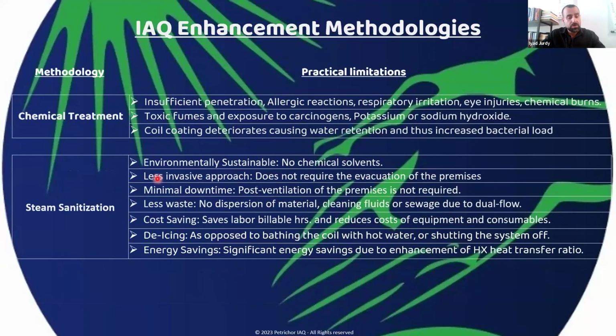The two most common procedures you'll find out there are chemical treatment and steam sanitization. Chemical treatment is the conventional way, the only way before we started using steam, which gives better results. With chemical treatment, we use a small hand pump and literally spray chemicals, acid, on the front of the coil. There's no penetration through the coil, it only cleans the surface.